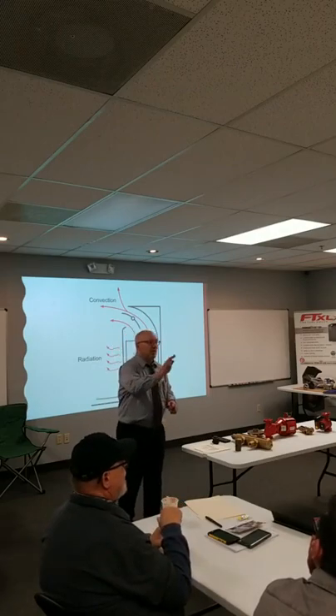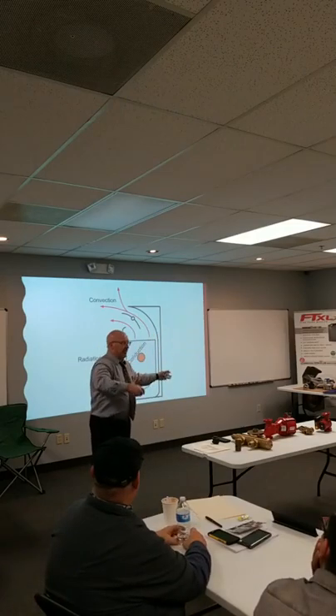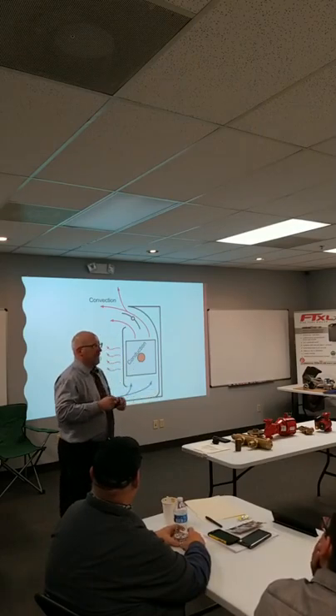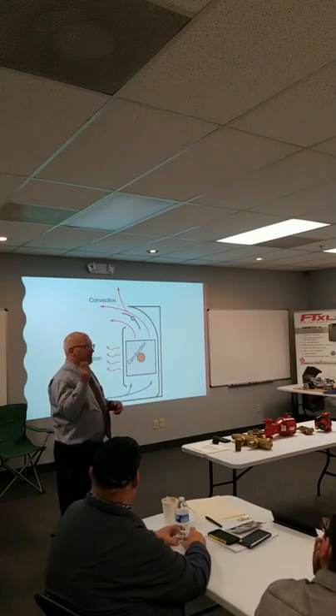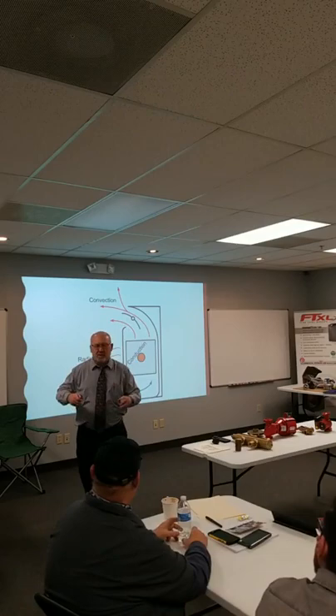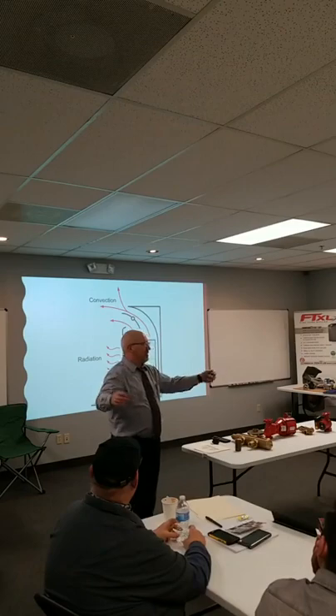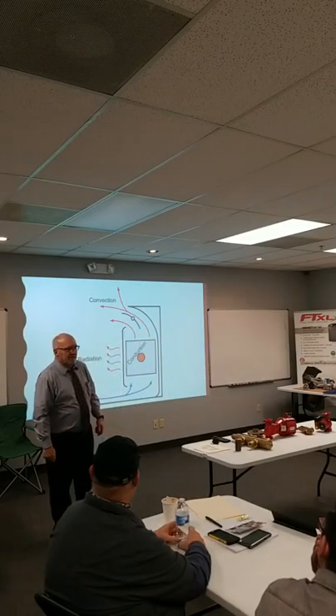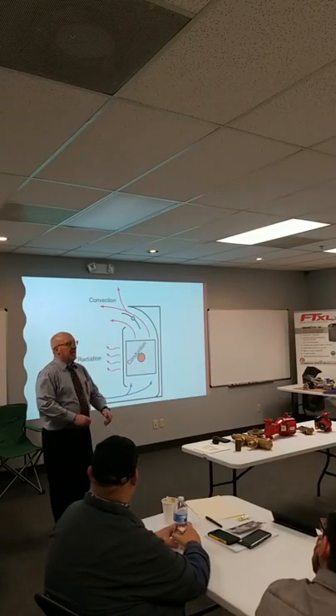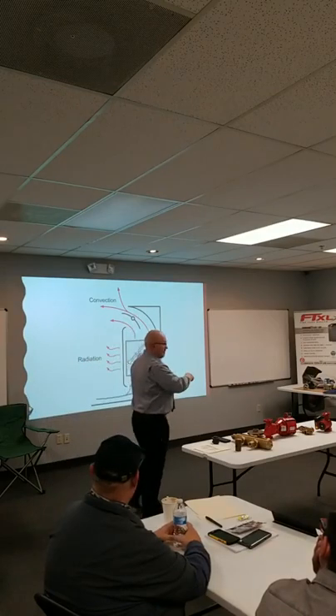The best one was a big house in Wade Hill. A beautiful, big old family room with beautiful hardwood floors. They said, we cannot get this room any higher than 62 degrees. We crank it up to 80 and we can't get it there. I'm going, that doesn't make sense. So we walk into the room. This table had to have been almost as long as this room, a big old wood table. I said, oh, that's a gorgeous table, but I really wasn't looking at the table. I was looking at the ornamental rug underneath the table, and there was about a foot all the way around of the wood floor.